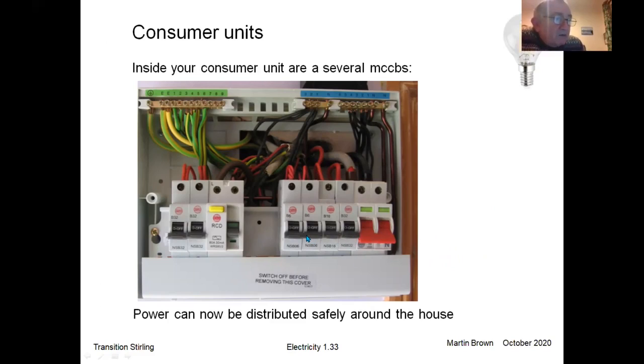These are the molded case circuit breakers. You can see they've got numbers on here. I hope you can see anyway. This one says B6. This one says B16. This one says B32. Those are the amperes at which they're safe to work. So the 6 ampere circuit, if you notice, has got relatively thin wires coming out of it. That'll be a lighting circuit. So we've said 6 amps, that's enough for the lighting in the house.